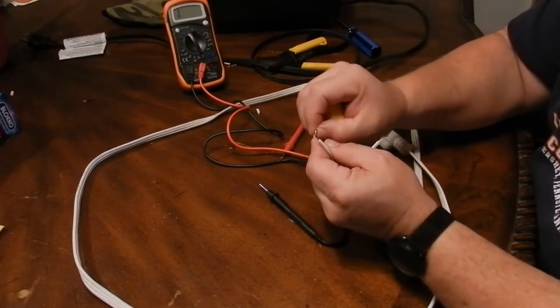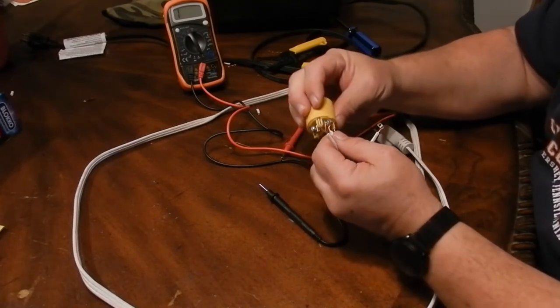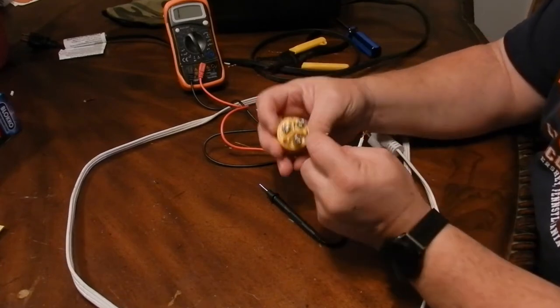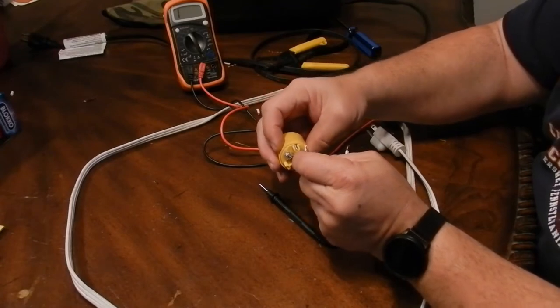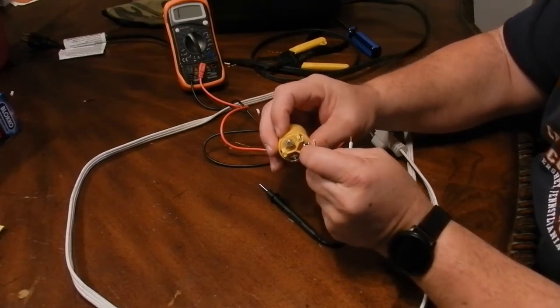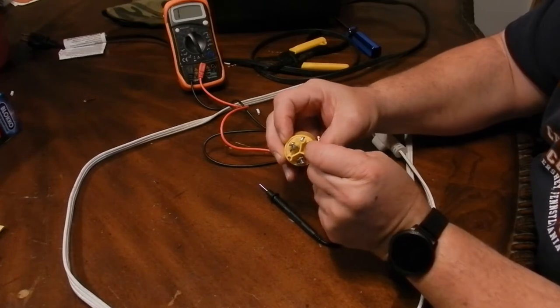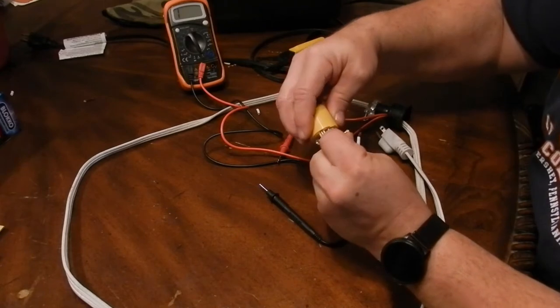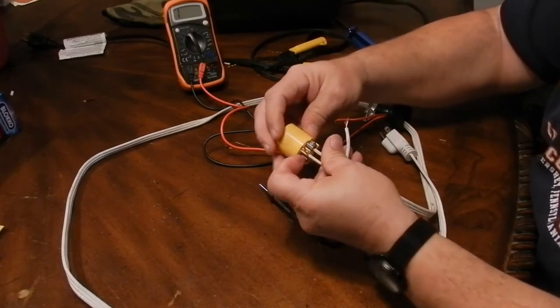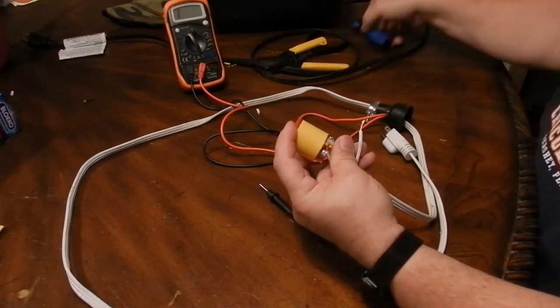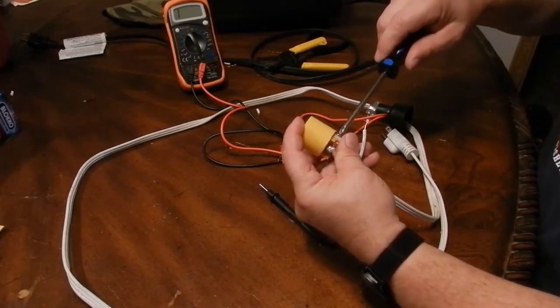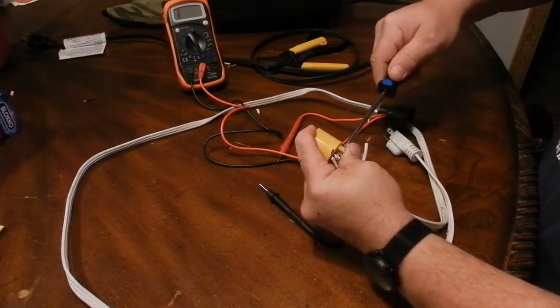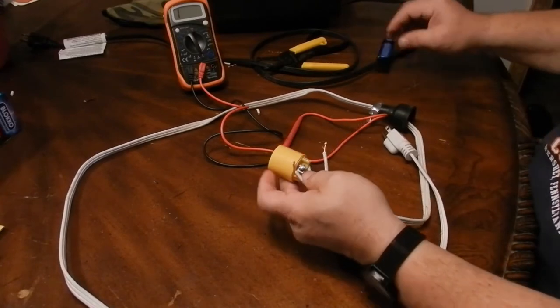So I'm going to take this to where the middle one is on the other side. And I'm going to curl it in the direction that it spins underneath. I'm going to put this underneath the plate. The plate is actually like a washer. So when you're turning the screw, you're not spinning the wire itself. And it clamps it down. So I'm going to stick this around and then I'm going to screw it down. I don't use a power tool because it's a very short screw and you don't want to strip it out.